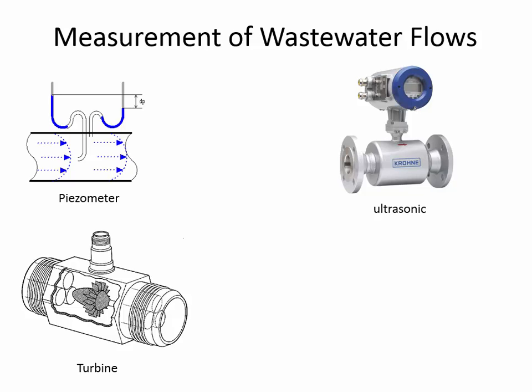That's what an ultrasonic flow gauge is able to do. It sends very rapid acoustic signals through the flow, reflecting them off particles or air bubbles passing through. It's basically tracking particles over time very quickly, knowing how quickly particles make their way through the test section, and quantifies that into a flow rate based on the known cross section of the pipe and the relationship between flow at some depth and the average flow rate. An ultrasonic flow meter has real big advantages — there are no moving parts.